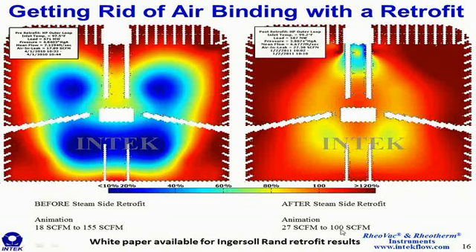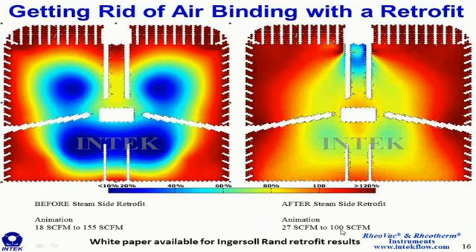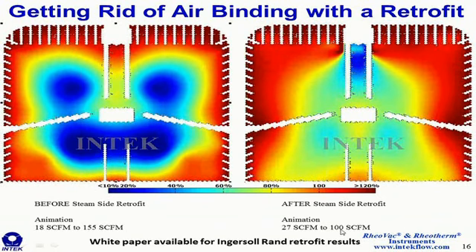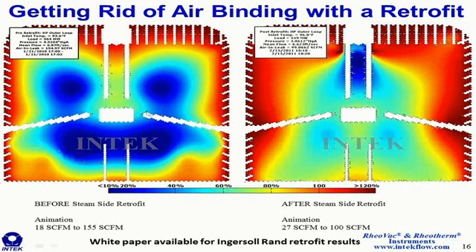So you should see the animation progressing, and you can see the pre-retrofit performance is the air binding has now extended all the way to the periphery of the tube bundle. The air is enveloping more tubes, causing back pressure to rise. But the post-retrofit profile, all those blue regions are gone, and the air is being concentrated to the new air removal sections. So essentially, this condenser is now more immune to air in leakage, and I'd like to show some test data in the tables below these plots to illustrate that point.